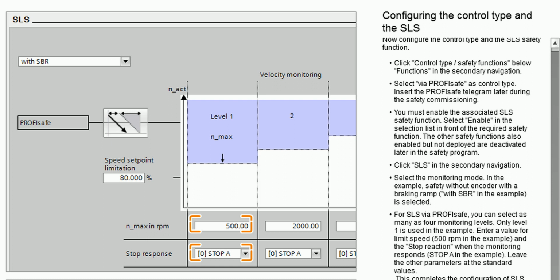Enter a value for limit speed, 500 revolutions per minute in the example, and the stop reaction when the monitoring responds, STOP A in the example. Leave the other parameters at the standard values. This completes the configuration of SLS. In the next step, configure the test stop.